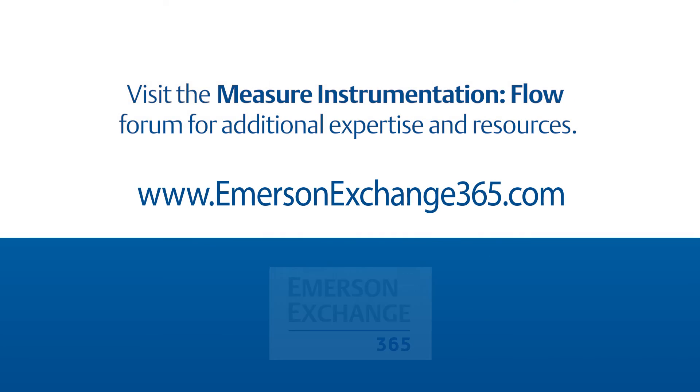Some additional benefits particular to the Emerson solution for these noisy applications is a great suite of advanced diagnostics. In addition to getting that stable flow signal and being able to control, they can also get all kinds of additional information about what's going on in the process. We have things like process noise detection to help optimize performance, and smart meter verification, which can really help simplify the maintenance routine around that meter. Especially in the oil field, with more and more environmental regulations coming about for what's going down hole, there's a need to verify the meters making that measurement. Smart meter verification is a great way to simplify that — a push of a button, the test runs, you get a pass/fail result, and if you need to report for compliance we have tools to help with that as well. To learn more about this product, head to Emerson Exchange 365 and engage our experts to learn more.